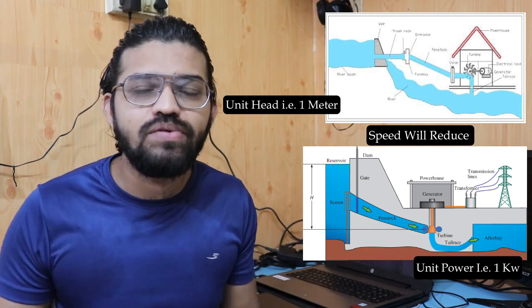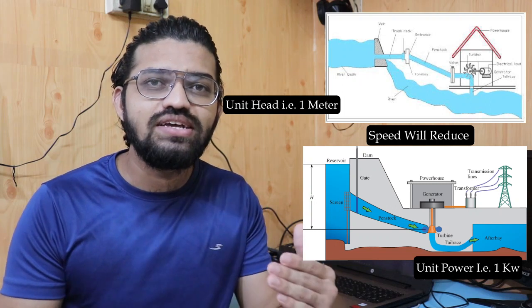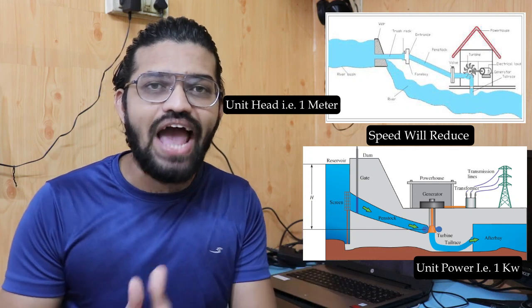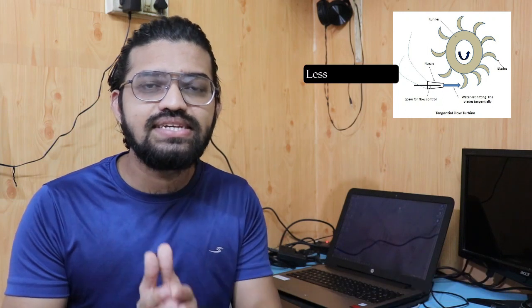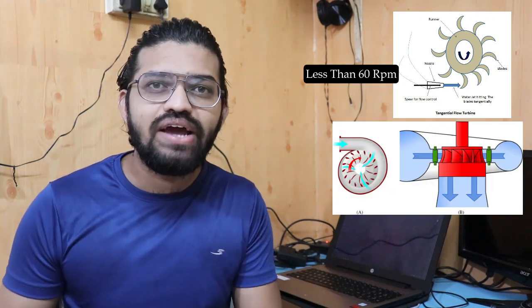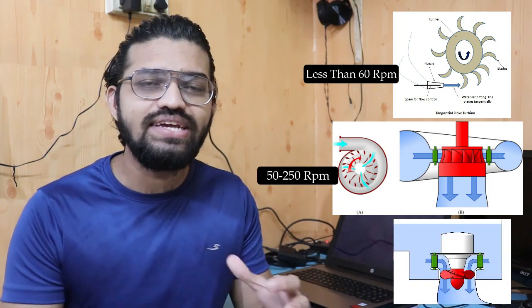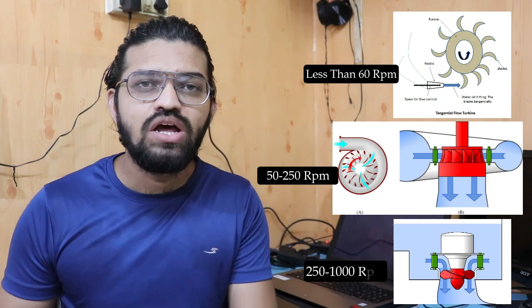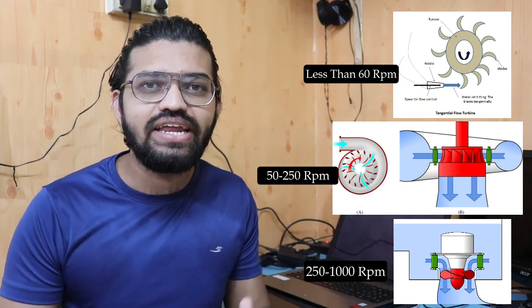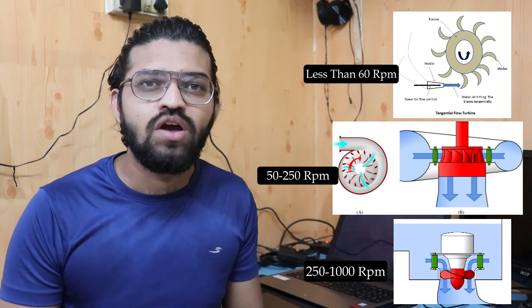The specific speed is used to differentiate between impulse and reaction turbines. The impulse turbine — the Pelton wheel — has specific speeds less than 60 RPM. The Francis turbine ranges from 50 to 250 RPM, and the Kaplan turbine has higher specific speeds ranging from 250 to 1000 RPM. So specific speed is the key criterion used to distinguish between these types of turbines.